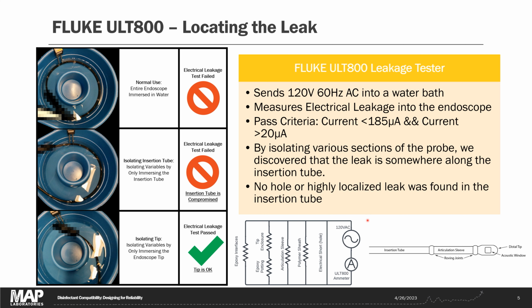When using the Fluke ULT 800, one test lead gets plugged into the back of the endoscope, and the other test lead sits in a water bath. In normal usage, you immerse all of the patient contact surfaces in the water bath. The Fluke ULT 800 generates 120 volts AC and measures the current leakage through the endoscope into the water bath and to that other test lead. The pass criteria here are that the current leakage must be less than 185 microamps. This other check, that the current is greater than 20 microamps, is basically just a check to make sure that you didn't forget to plug in one of the test leads.